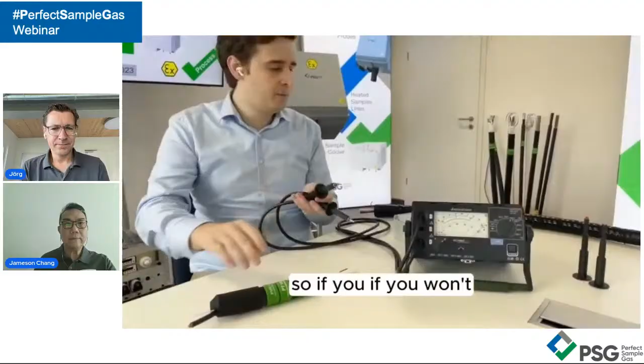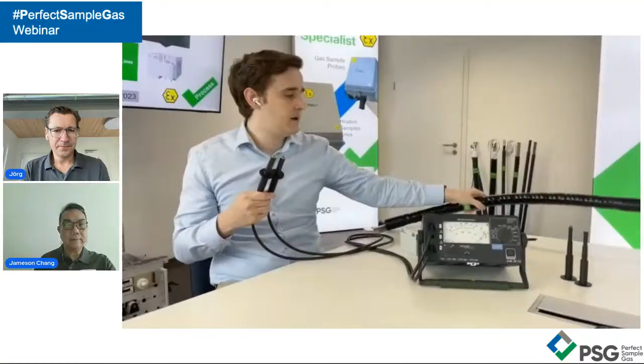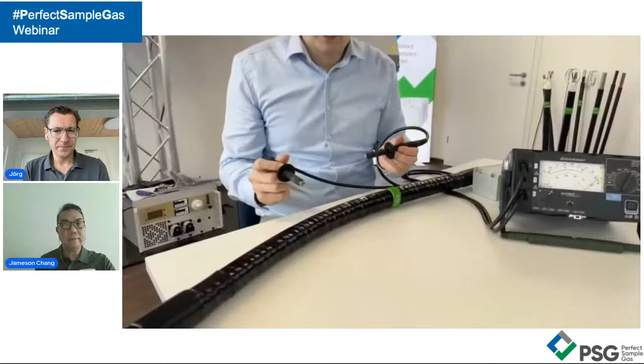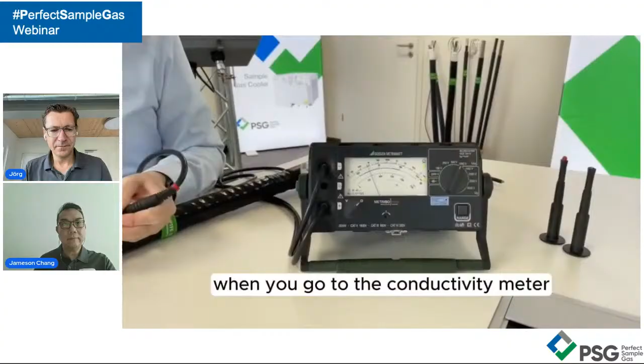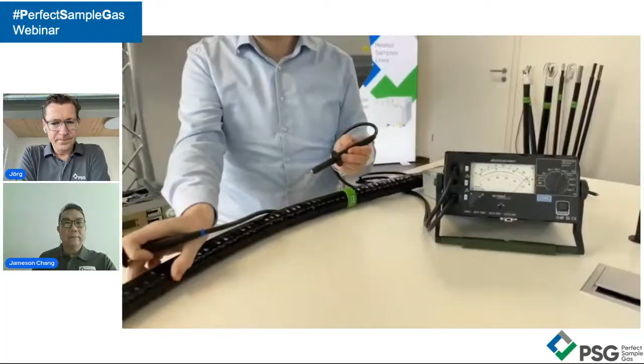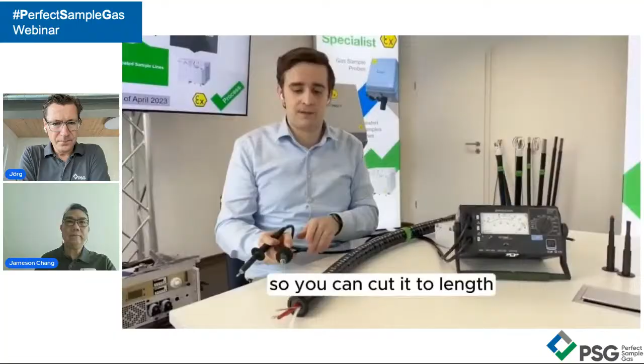So if you won't use just a regular junction box in an ATEX area, why use a regular heated sample line for the ATEX area? Instead, we would recommend to use our ATEX 3 heated sample line. What you can see over here, when you go to the conductivity meter, there's a fully conductive jacket on the outer side, and the conductivity even goes up until the cap. So even the caps are conductive, and you can place these caps yourself. So you can cut it to length, or we can also place the caps for you. And even when you cut it to length, you have the full ATEX certificate for the whole line.